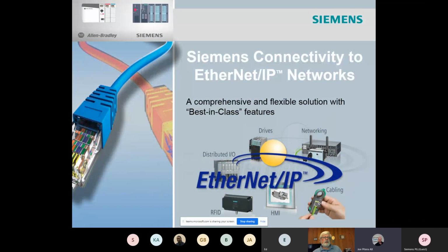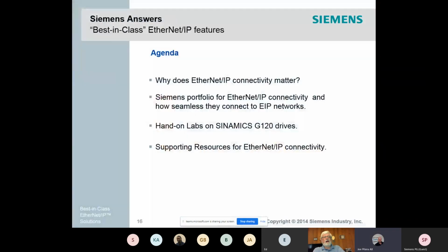Siemens and Rockwell products working together? Yes. That is true, we can do that. Today's agenda: why does Ethernet IP connectivity matter? Siemens portfolio for Ethernet IP connectivity and how seamlessly connected Ethernet IP networks are. I will have the hands-on lab here live, commissioning a G120 drive and connecting it via Profinet to a Siemens PLC. And then with one parameter change in the drive, I can talk to a Rockwell controller as well. Our HMI can support talking to both the Profinet and Ethernet IP simultaneously.